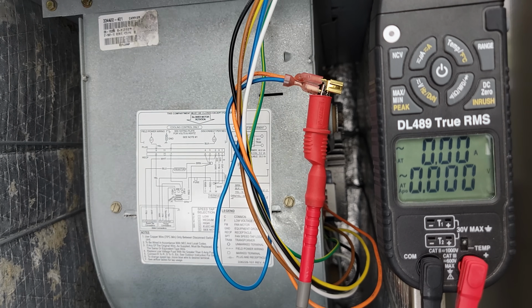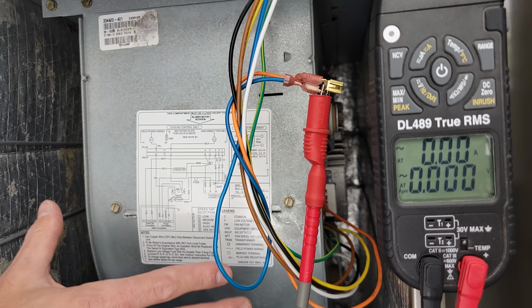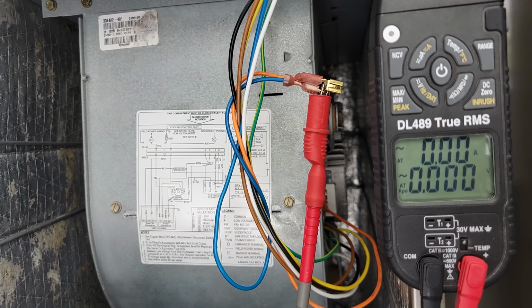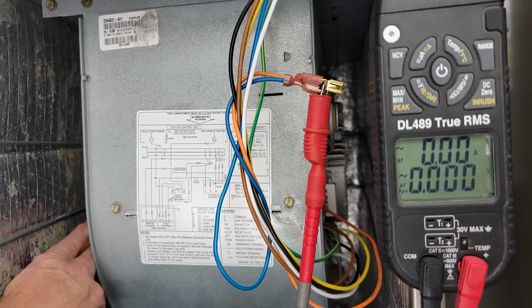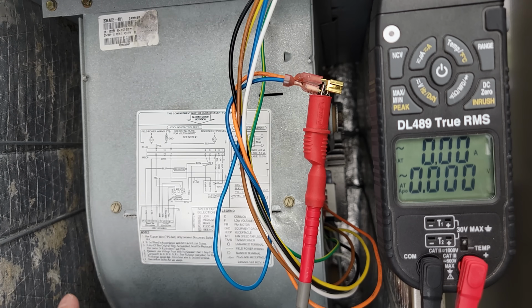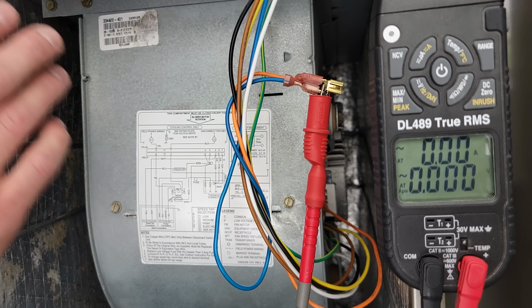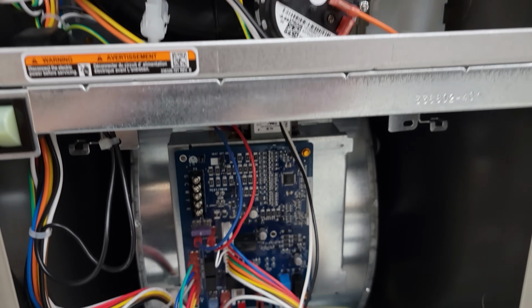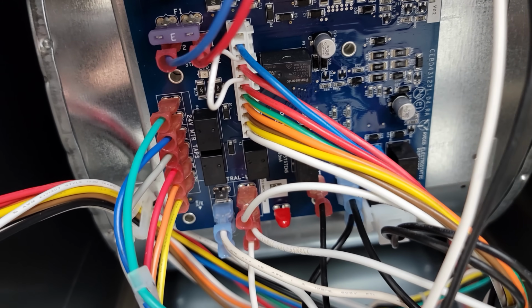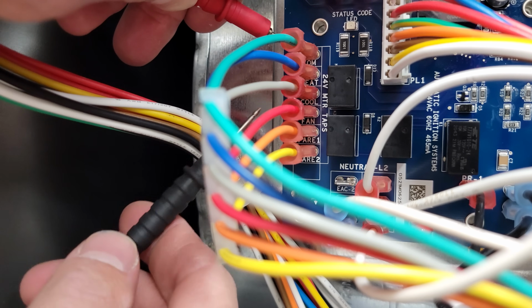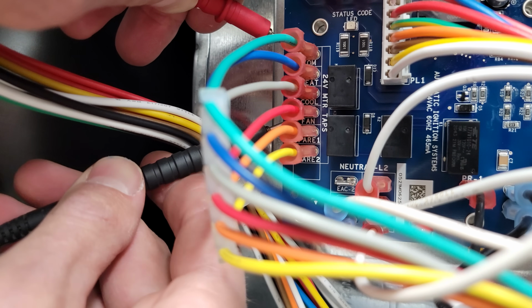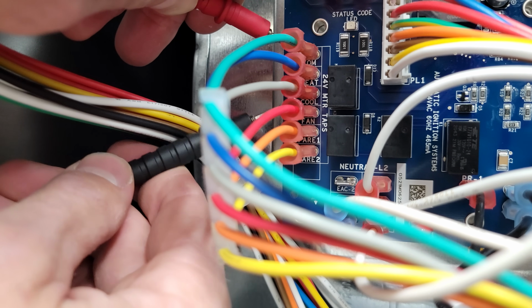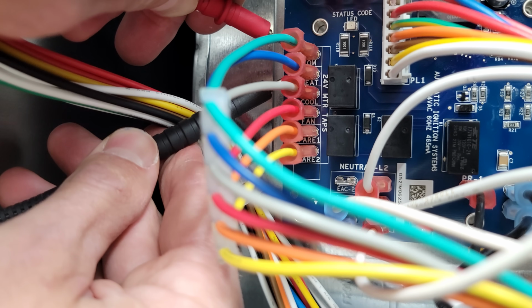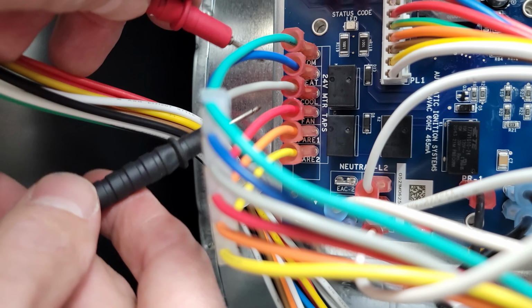If we had 24 volts on here and the blower motor did not turn on, and we had power to the blower motor, and when the power was off, this wheel back here was free spinning, it wasn't a problem, then we would know that we need to replace that blower motor. And so you don't just replace the module by itself, you do replace the blower motor as well. Here we have a 120 volt gas furnace, and let's look at the ECM motor taps. Now this is normally what it's going to look like inside of a 120 volt gas furnace, and you can just check for your 24 volts between common and fan, common and cool, or common and heat in order to determine if your blower motor should be running.